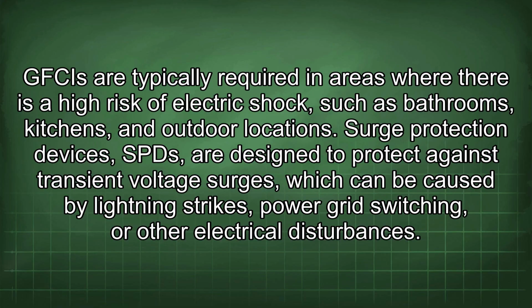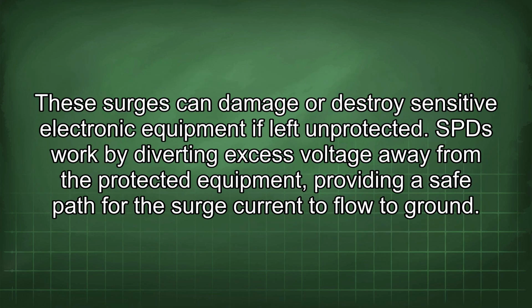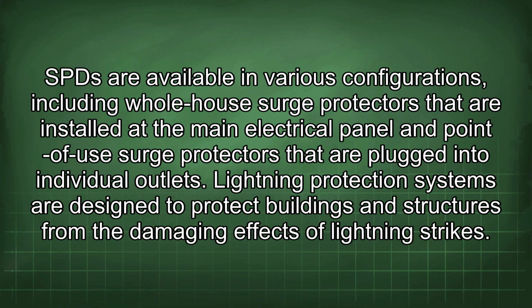Surge protection devices, SPDs, are designed to protect against transient voltage surges, which can be caused by lightning strikes, power grid switching, or other electrical disturbances. These surges can damage or destroy sensitive electronic equipment if left unprotected. SPDs work by diverting excess voltage away from the protected equipment, providing a safe path for the surge current to flow to ground. SPDs are available in various configurations, including whole-house surge protectors that are installed at the main electrical panel and point-of-use surge protectors that are plugged into individual outlets.